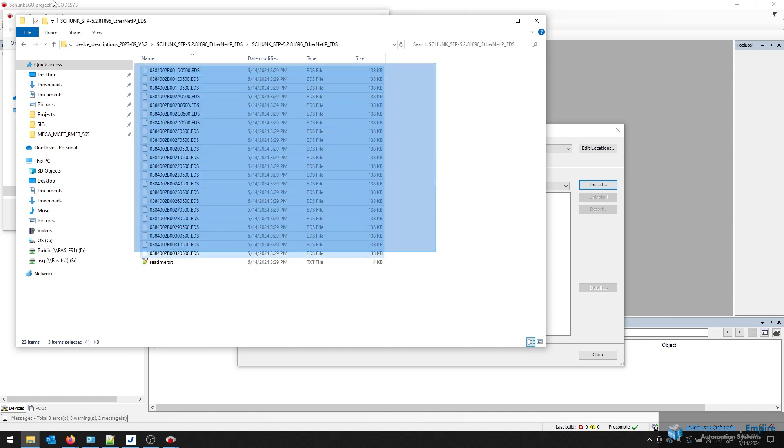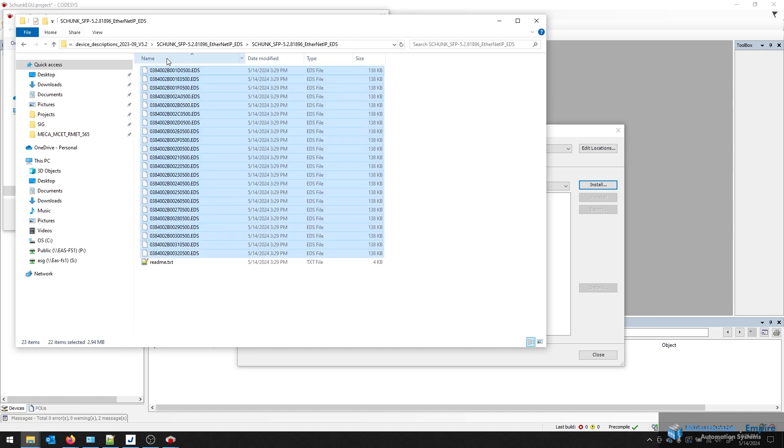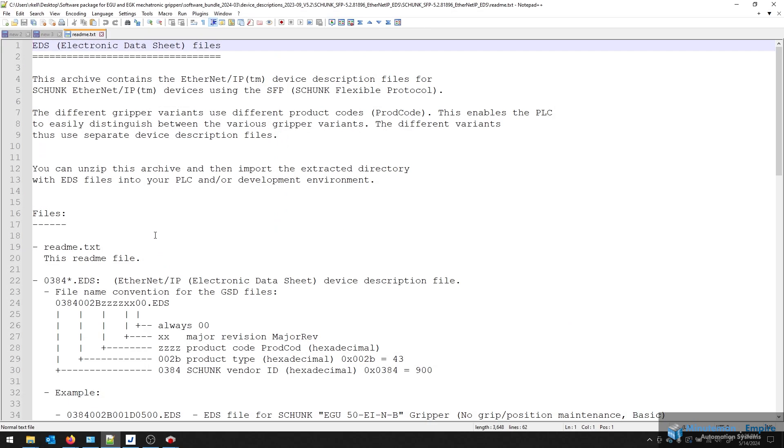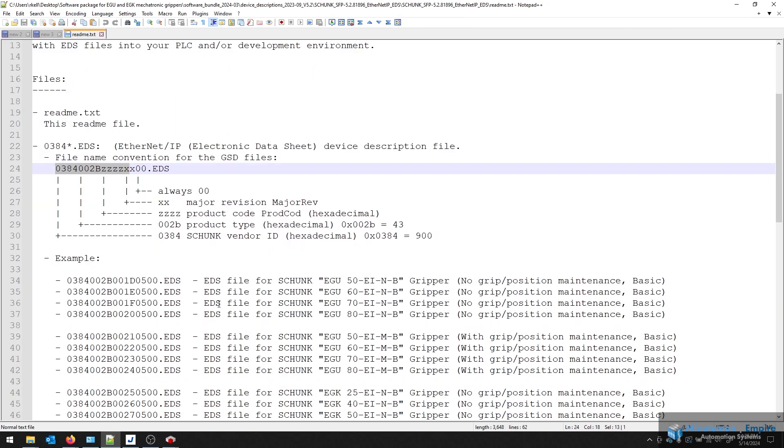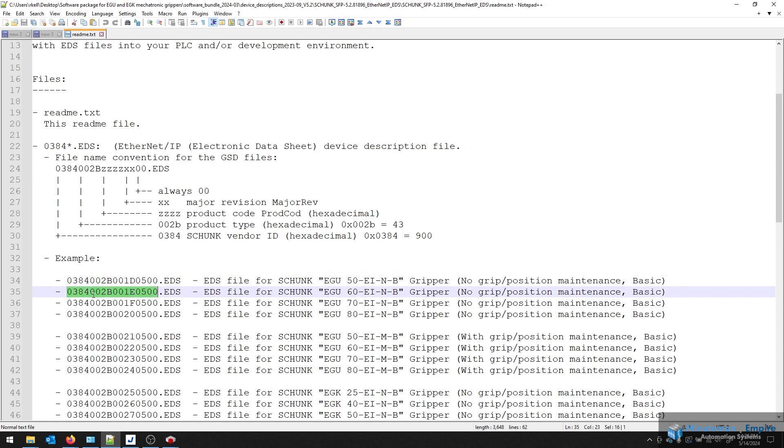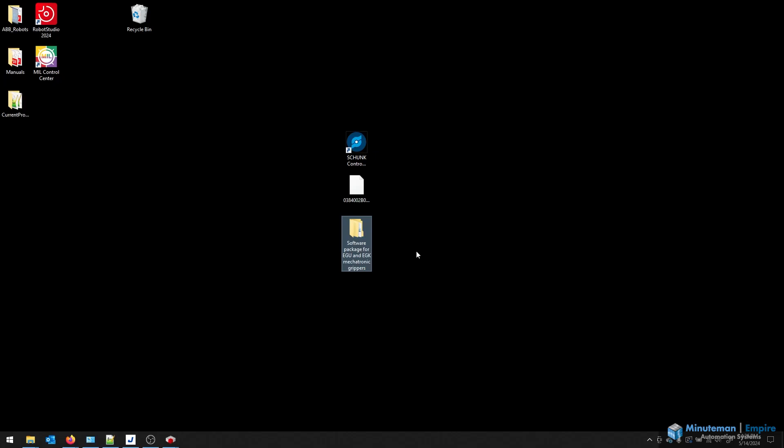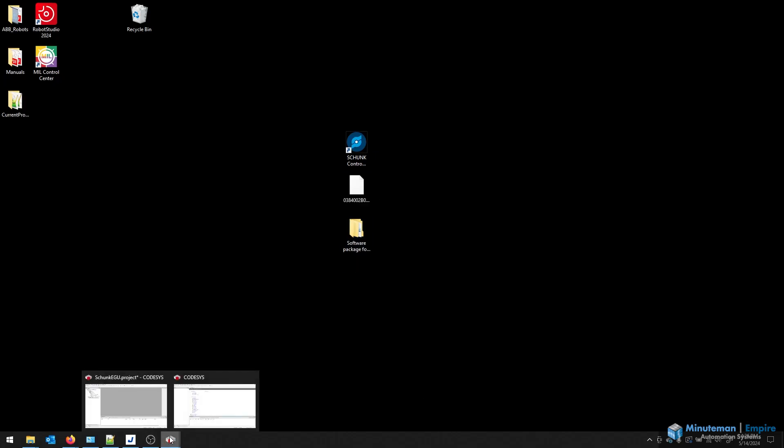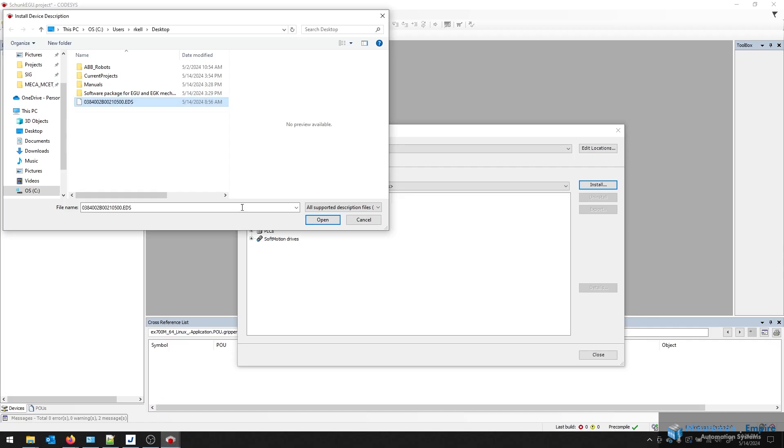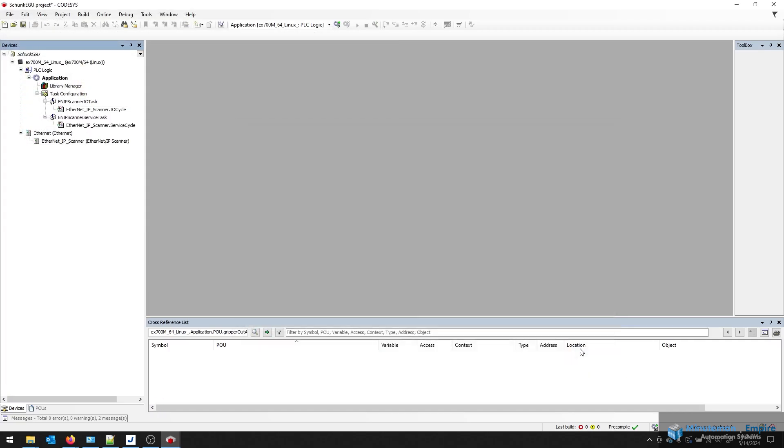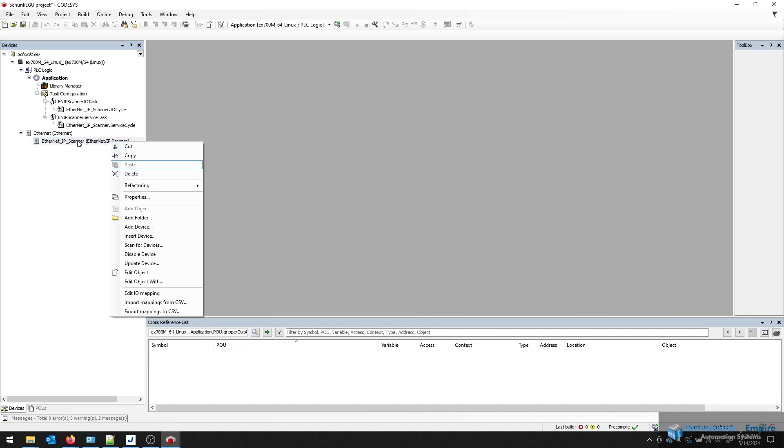And then find the specific EDS file. You'll see here that there are several EDS files. If you open up the README file, it will explain the various codings here. So depending on which SCHUNK EGU model you're using, that will change which EDS file you're going to need to use. In our case, we need this file. So I've moved that file to my desktop, making it easier to find. Open that up, and it's going to add that to my repository. And now I can add that device here.